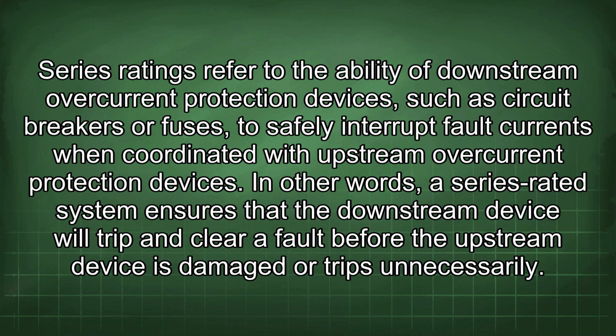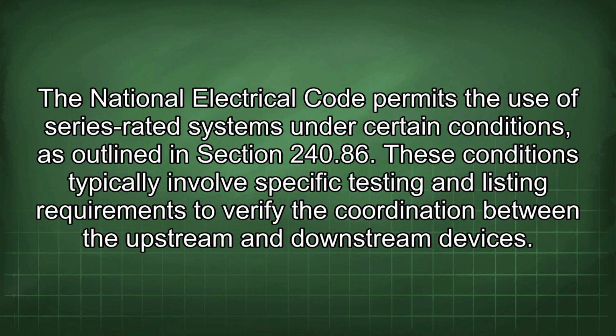In other words, a series-rated system ensures that the downstream device will trip and clear a fault before the upstream device is damaged or trips unnecessarily. The National Electrical Code permits the use of series-rated systems under certain conditions, as outlined in Section 240.86. These conditions typically involve specific testing and listing requirements to verify the coordination between the upstream and downstream devices.